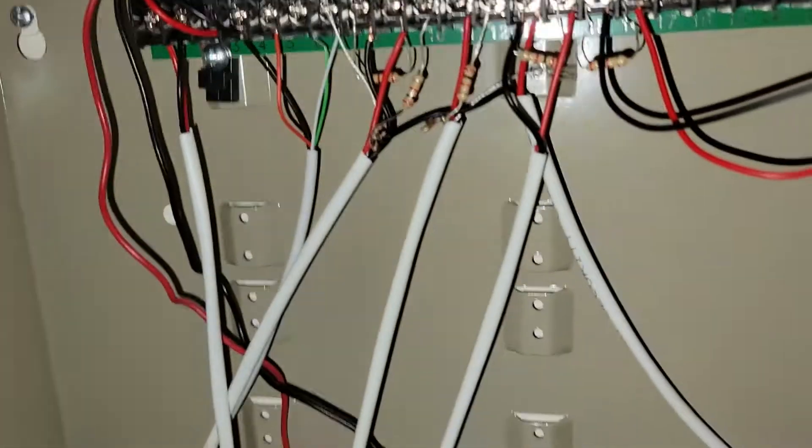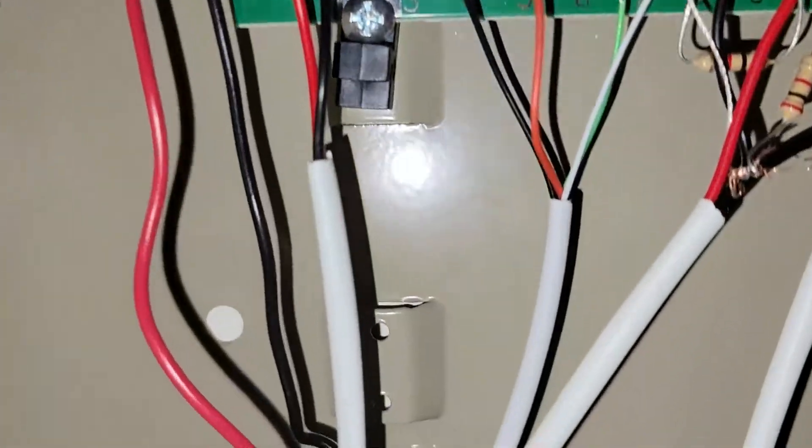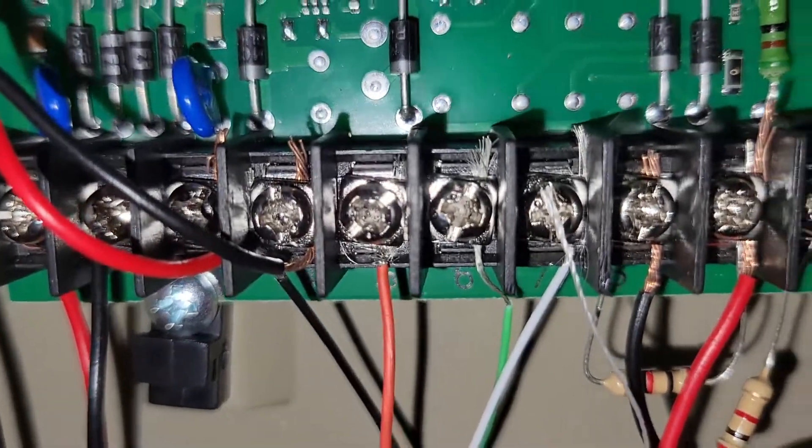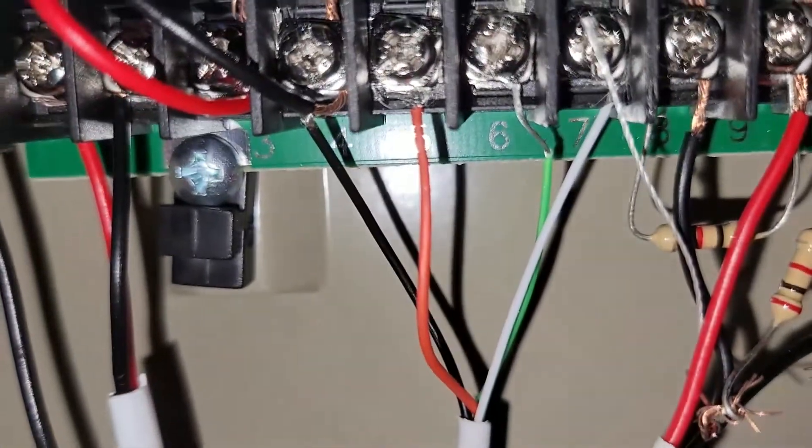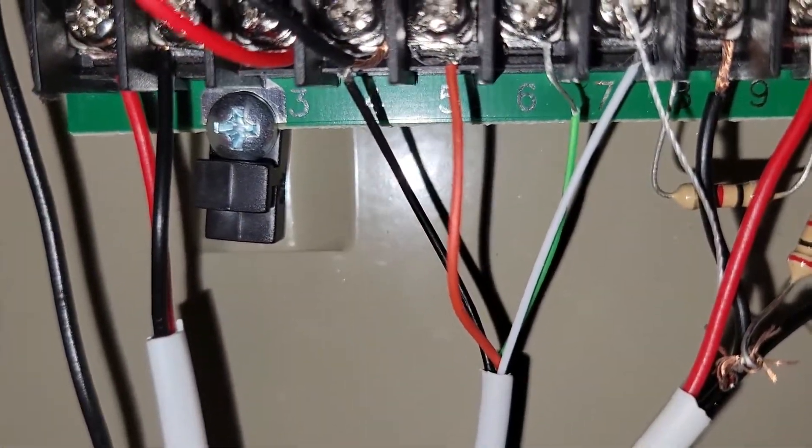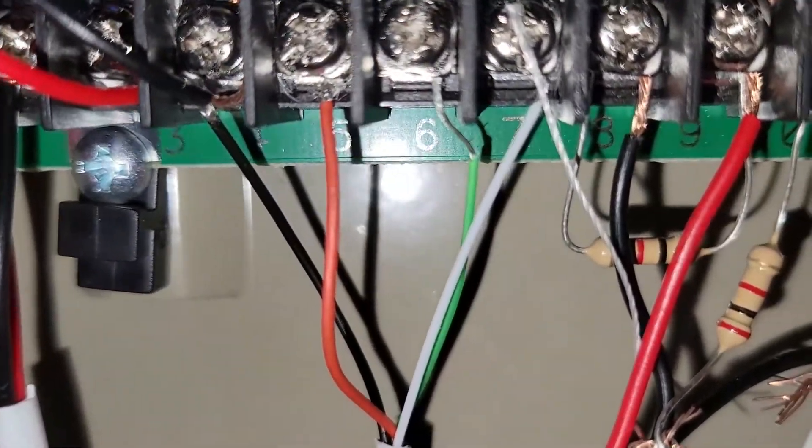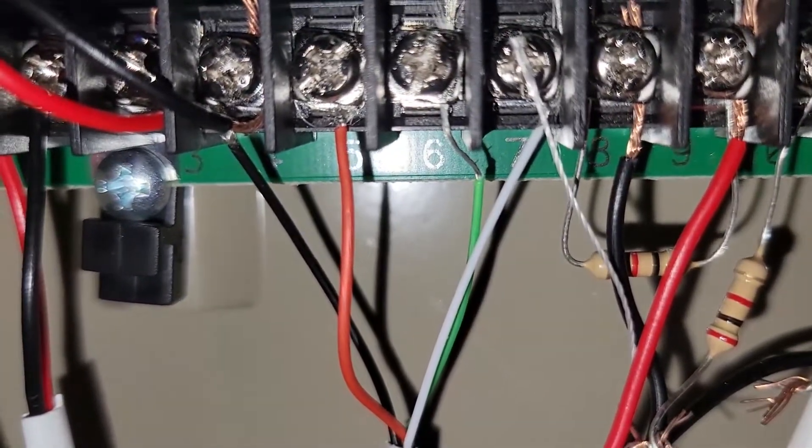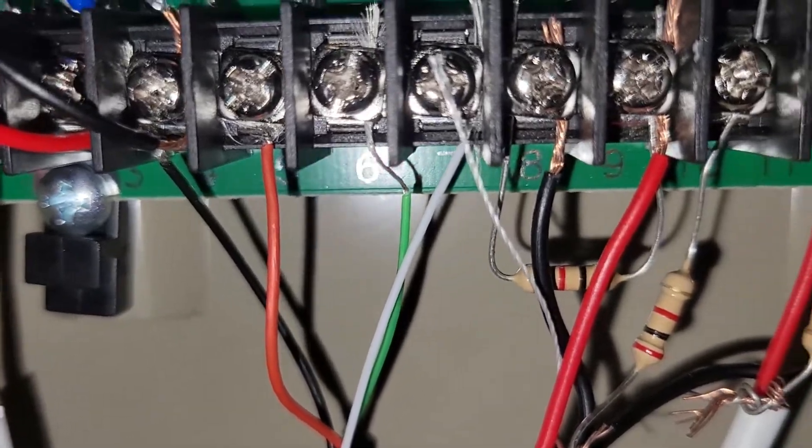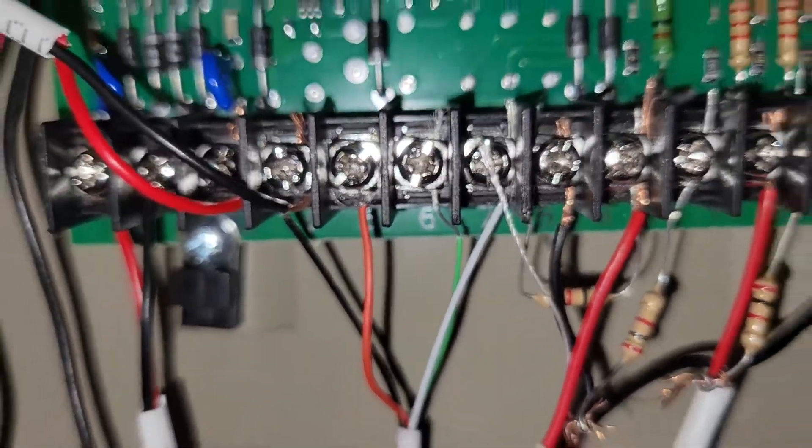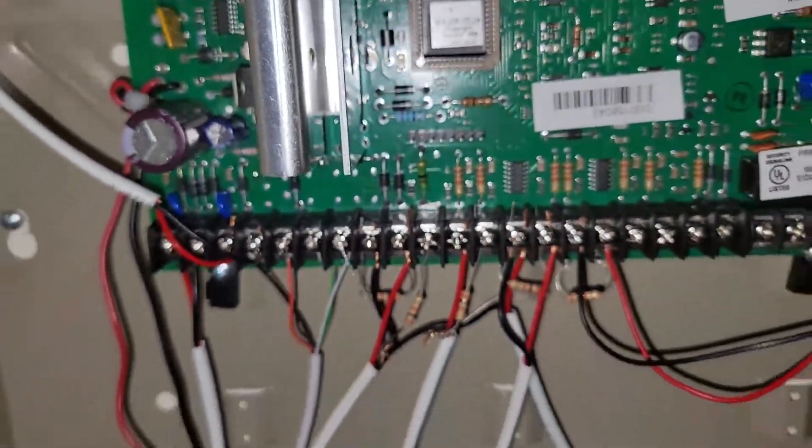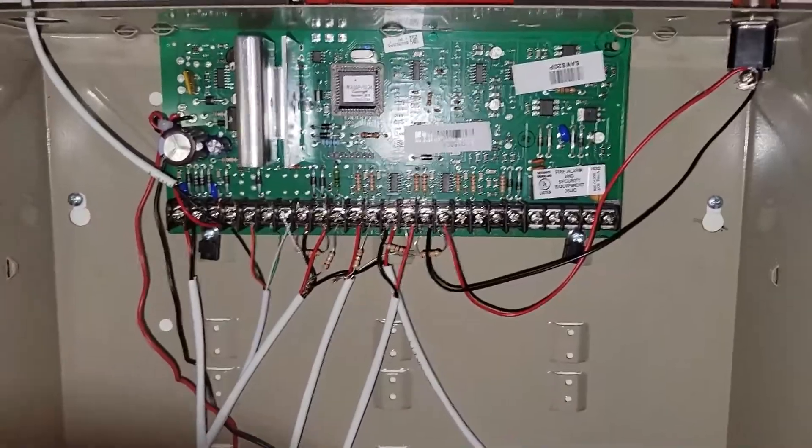Terminals four, five, six, and seven are your keypad terminals in here. As you can see, number four you'll put the black wire, number five you'll put the red wire, number six you'll put the green one, and number seven you'll put the white one into your control panel.